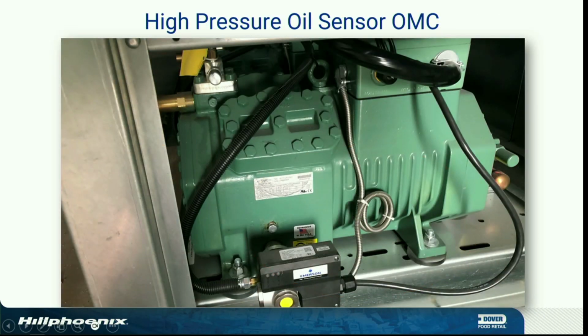Here's an Emerson OMC oil switch. Same thing. We got a green light, yellow light, and a red light. I gotta tell you guys, nowhere on the top of that switch does it say this is a step. We had one sent back under warranty because it broke the yoke up here on the flange. The flange broke. Guy sends it back, has a boot print right on it in oil and dirt.